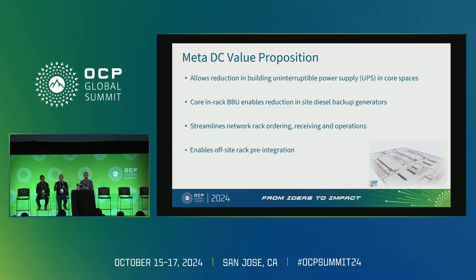It's got in-rack backup. Now we can start to homogenize the power within our data center. We can start to scale down our building-scale UPS, which also allows you to start to reduce your building footprint — very good for design, engineering, and construction. So a lot of synergies there. Another great synergy: once it's a compute rack, for the last 10 years we've got an ordering process, a delivery process, an installation process, and off-site integration of compute racks. Instead of maintaining two processes for network racks and compute racks, we can have a unified process across the fleet — which is a great advantage.